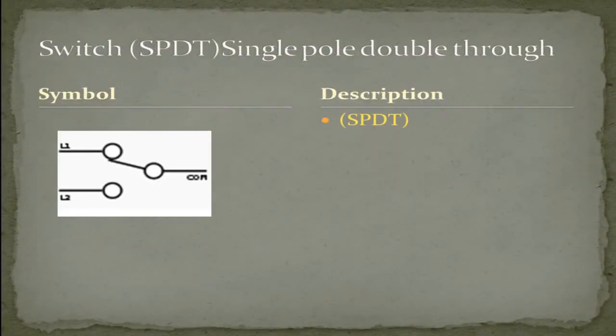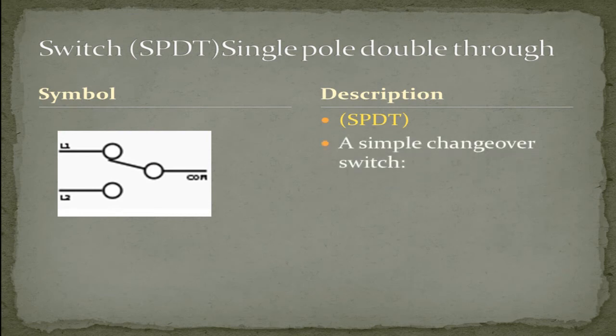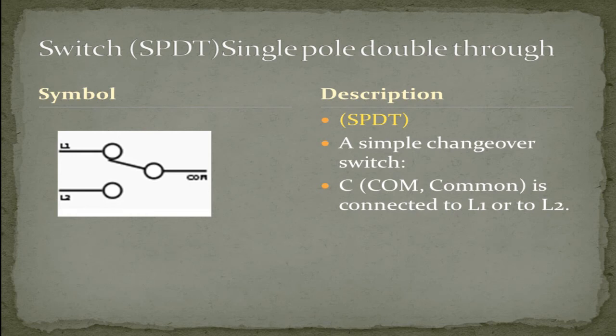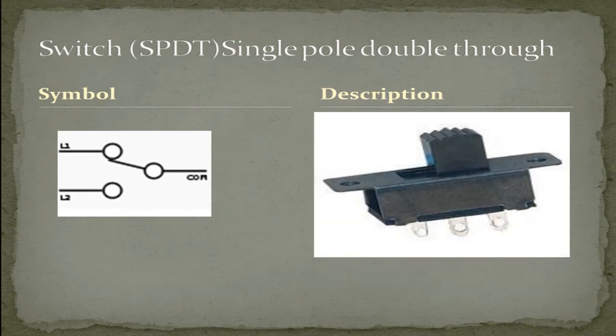A single pole, double throw switch. A simple changeover switch. C (the common) is connected to either L1 or L2. As you can tell, you have one common wire that is capable of controlling two circuits. Example: a high-low switch. In this picture, you can see a single pole, double throw switch. And you can tell by the three terminals: the one common and the two lines.